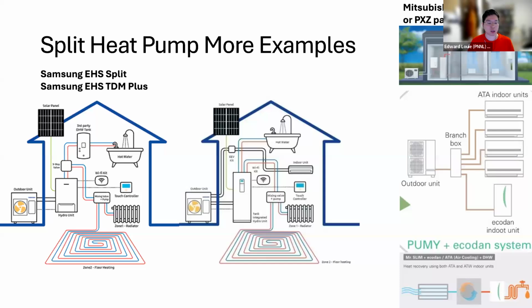Split heat pump systems can also do refrigerant to water in a heat exchanger inside. So like here in the Samsung system, they're diagramming that it can go into a radiant floor system. It can also go into panel radiators. Some of these systems are like the multi-split outdoor unit heat pumps, so there are multiple refrigerant ports. So you can have one refrigerant branch go into a refrigerant to water heat exchanger that sits inside the house, and another branch can go to a ductless heat pump head, for example.